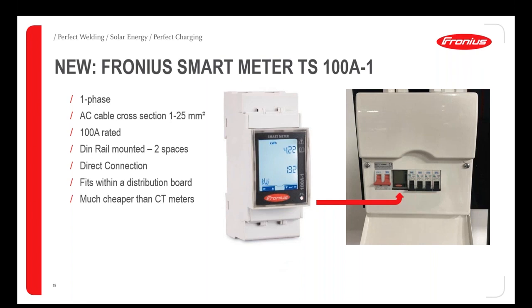You can obviously install it in a separate box next to your enclosure. That's always an option. But if you do have difficulties with space, you've always still got the option of the CT meter. The Smart Meter TS100 has other advantages. It is rated to 100 amps, so it's suitable for almost all UK and Irish domestic installations, and it has a terminal cross-sectional area of 25 mil. It's designed to be used with most residential incoming connections. It's also important to note that this meter is significantly cheaper than the CT meters. So there's a significant cost benefit to using this meter rather than the CT meter, as well as potentially easier installation.